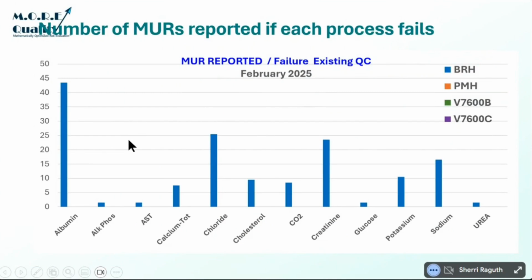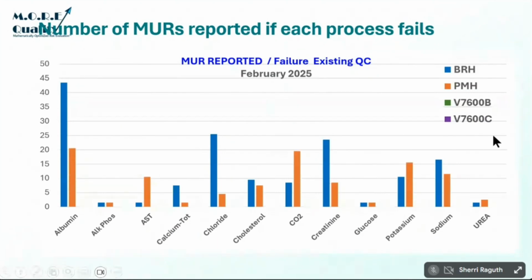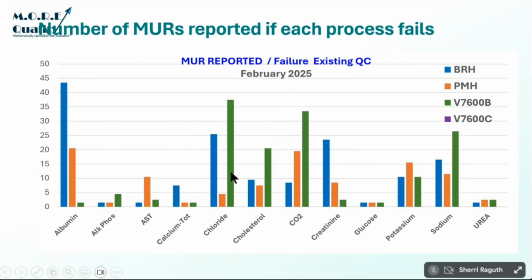Okay. Here's what happened with these labs. I'm looking here at 3 QC samples in each one of these from each one of these instruments. If this bar is at 3, because I designed it to detect 3 errors, so 1 error per day, if you're at the level of 3, your risk is acceptable. So you can see that it differs by analyte. It differs by instrument.